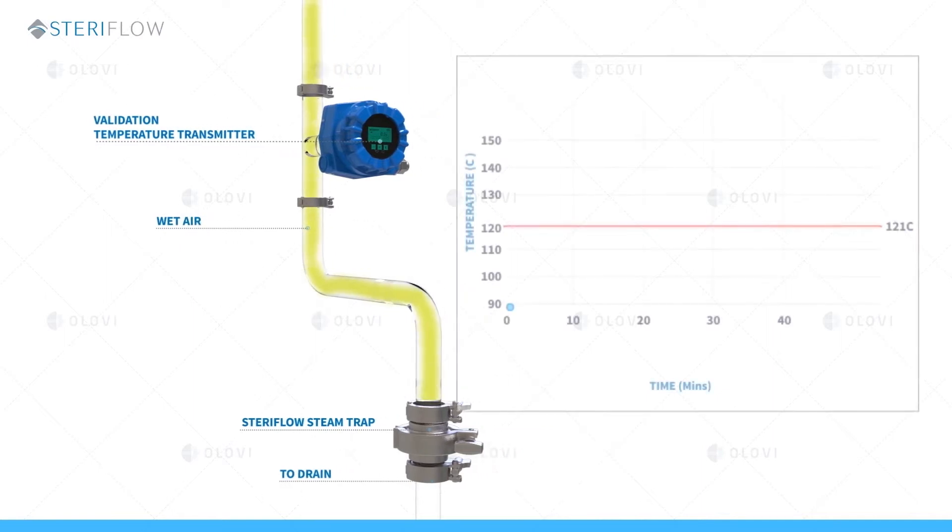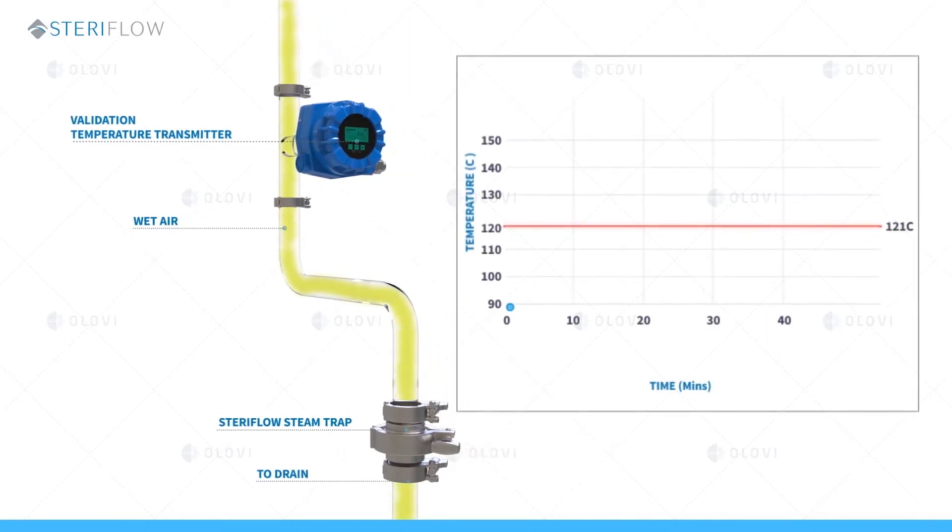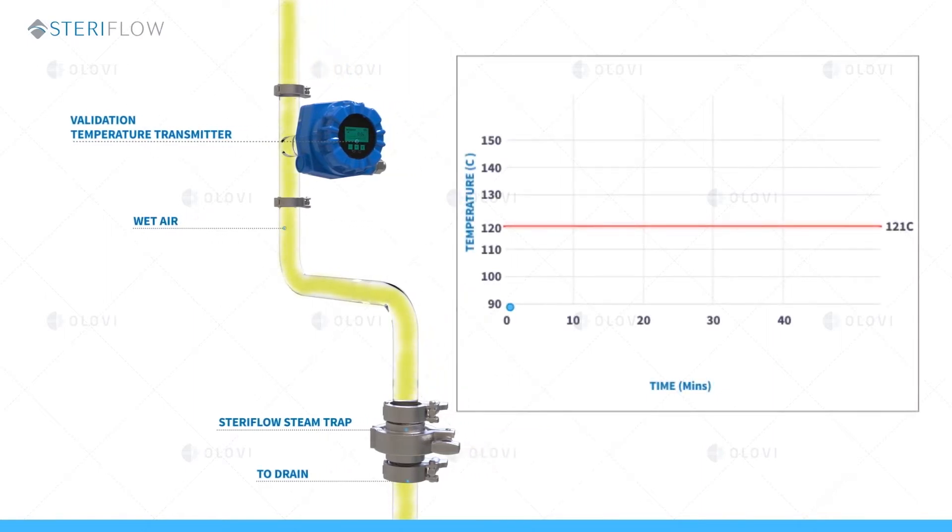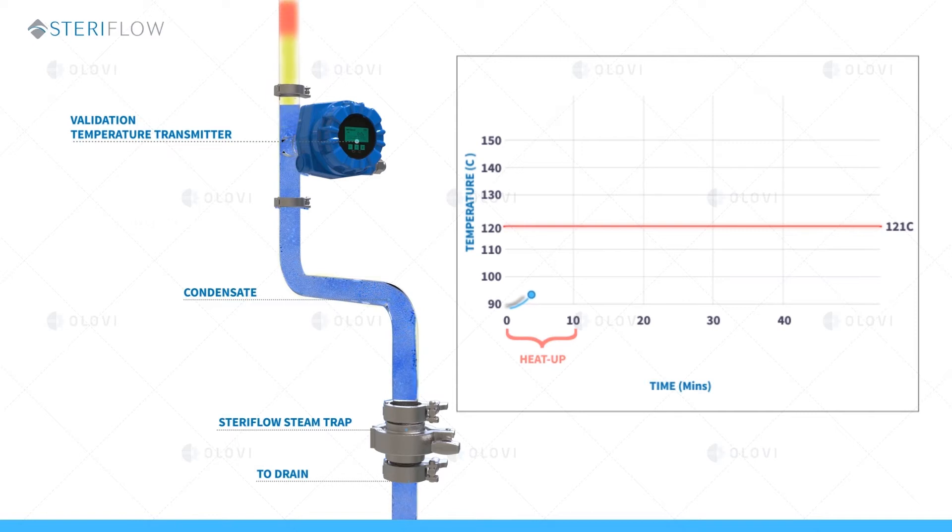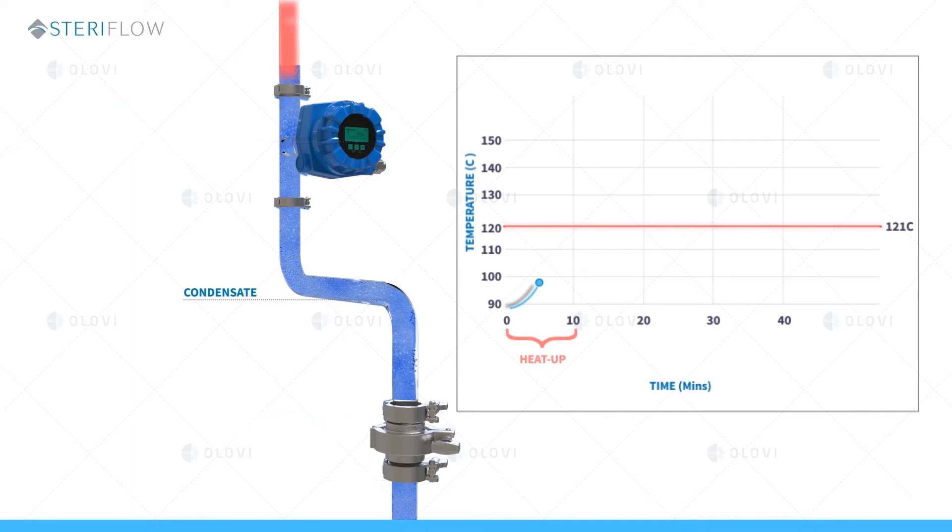What you're looking at is a temperature validated condensate drain line at the bottom of a process skid. Heat up describes the beginning of SIP when clean steam enters and begins to heat the system being sterilized. The steam traps are open enabling clean steam to push out insulating air and to remove condensate.